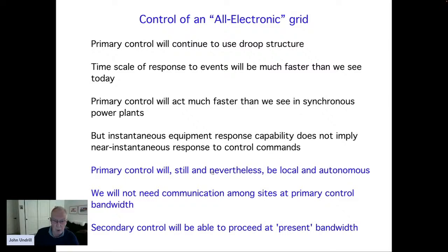We had a bad problem in a steel mill that I was involved with 20 years ago, where we had a control system that depended on signals being sent from turbine generators on the east side of the facility, about 4 kilometers away, to a large rolling mill on the west side of the facility. It was only 4 kilometers, but the relay equipment we used, which was the best that we could buy from the current name brand manufacturers, claimed that contact outputs would go from one relay to the other instantaneously. When we tried it and got our oscilloscopes out and looked at what was really happening, there was a time delay in signals going from one part of this control system to another of 50 milliseconds at the sending end and 50 milliseconds at the receiving end.